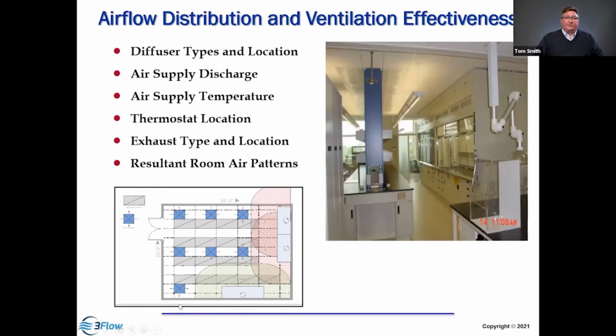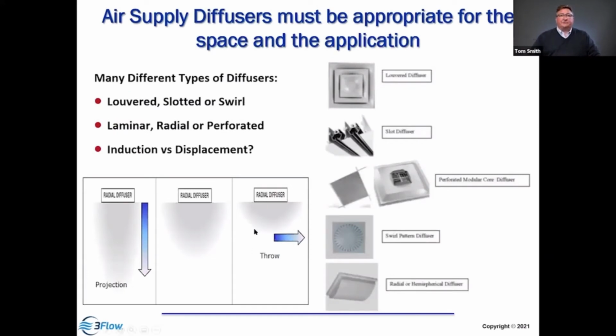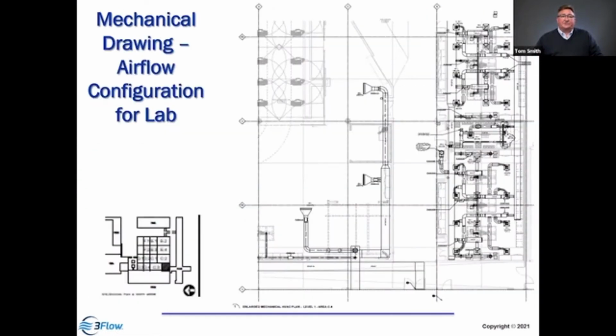The location of the air supply in the room is really important. So in this picture, you see the line of hoods. We have our air supply diffusers over the benchtop. Now they're close because they're only a couple of feet away. And when this was blowing cold air, it was dumping. But when it was hot air, it was blowing across the ceiling, and that was causing turbulence in front of the hood. So we recommend the diffuser should be at least 5 feet away from the hood. So if you drew a diagram here, you'd say the no-diffuser zone is 5 feet around that hood. There should be no diffusers in that zone. It doesn't mean it can't work with a diffuser in that zone. It just says it might be an issue. And there are so many different types of diffusers that we have to look at the projection and the throw of velocities from these diffusers and how it might impact the room airflow patterns and the performance of the hood. And we have a test called the cross drafts test to evaluate it.